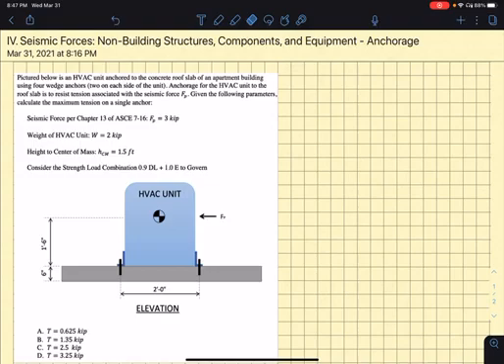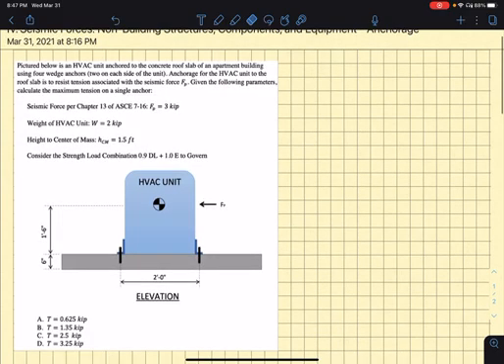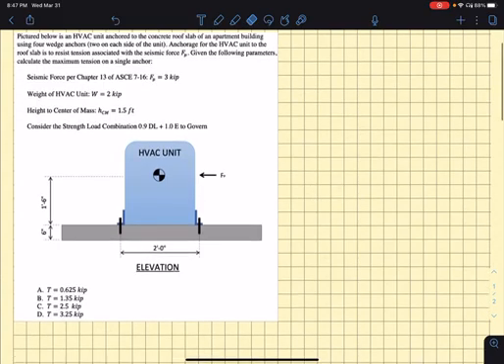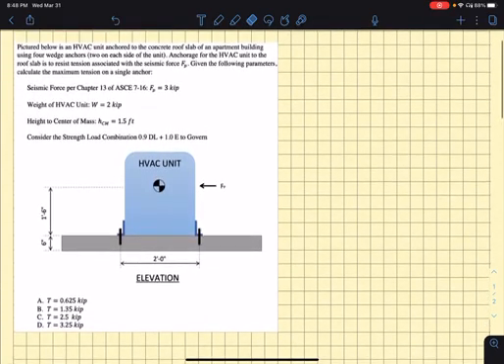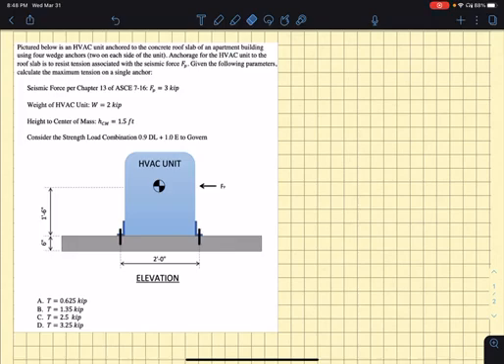So back to the problem. This specific problem falls under section 4 of the board's study plan for the seismic principles exam. The problem pertains to an HVAC unit which is anchored to a concrete roof slab on top of an apartment building. It's anchored with four wedge anchors, two on either side. The anchorage for the unit is meant to resist tension associated with the seismic force F_p. That seismic force F_p is calculated based on chapter 13 of ASCE 7-16, the non-structural component seismic force. It's given here in this problem statement, and we're just going to use that to design the anchor for the maximum tension.